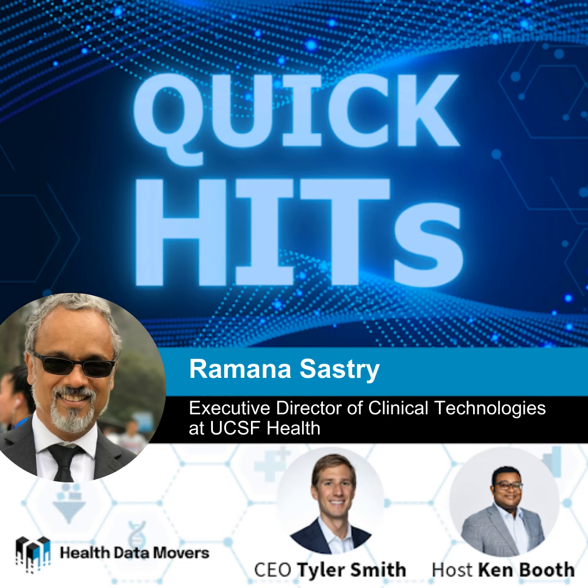I'd like to see technology management go into being able to tap into that and catch issues before they happen. If you see a specific variable starting to fluctuate or drift, we want to capture it before it actually fails, so we can schedule maintenance off hours so it doesn't impact patient care or lead to a device failure, which would definitely bring downtime. But with predictive maintenance, we get the additional ability to catch these things before they fail.